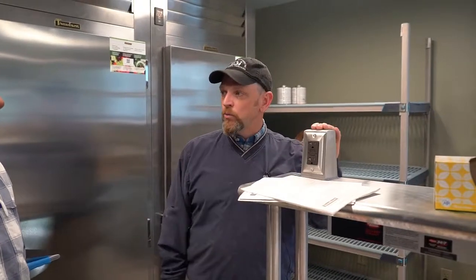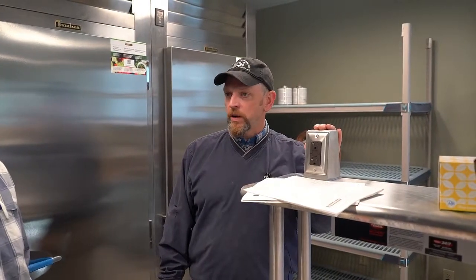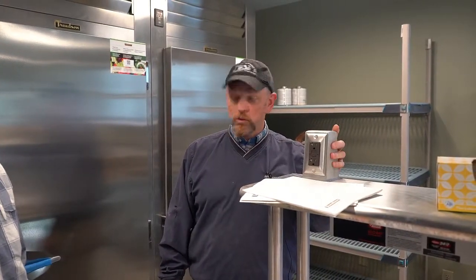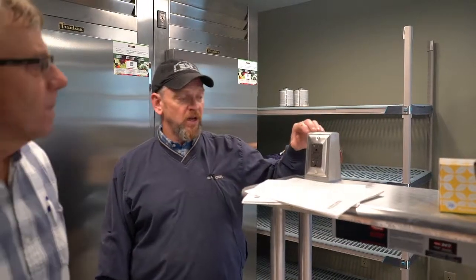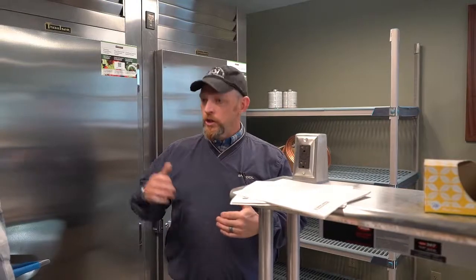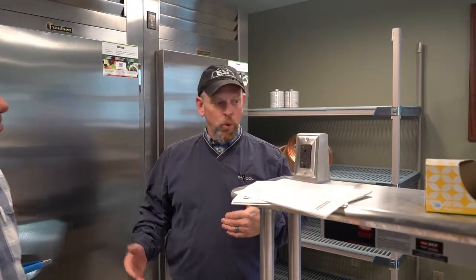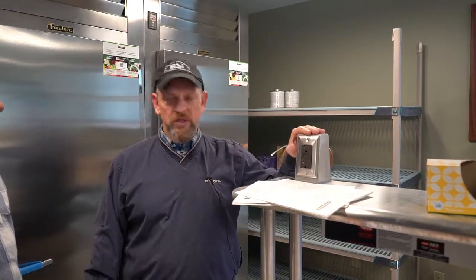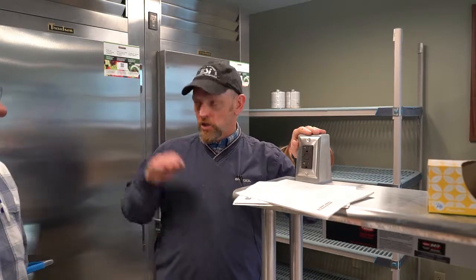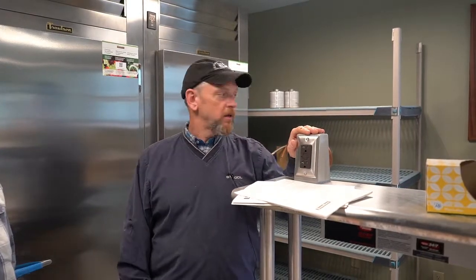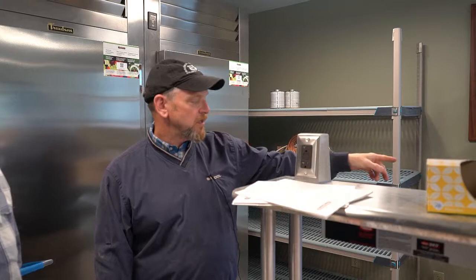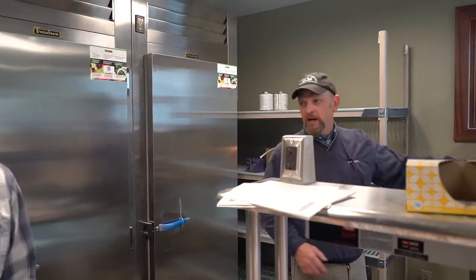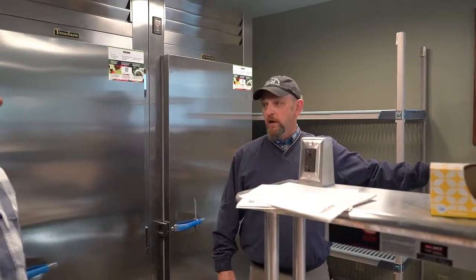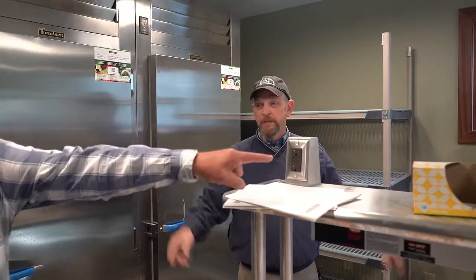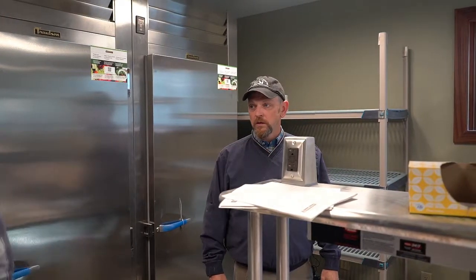The equipment came with some GFCIs already attached to the tables and whatnot. And because you can't have a GFCI outlet on a GFCI breaker, it doesn't work, where we have GFCI outlets, it's just on a plain breaker in the back. You can see some of those actually came with GFCIs, and we changed them out to standard. Those are the ones that you can bet we'll get the question on.